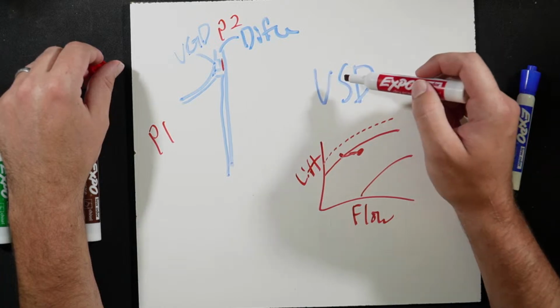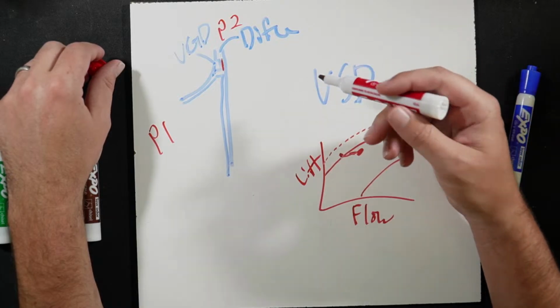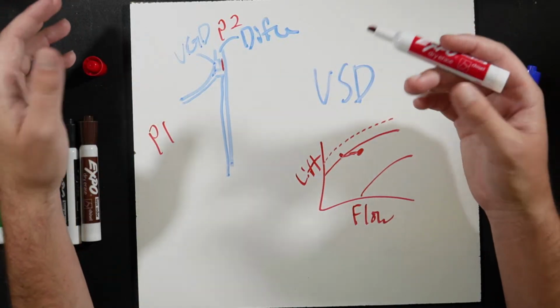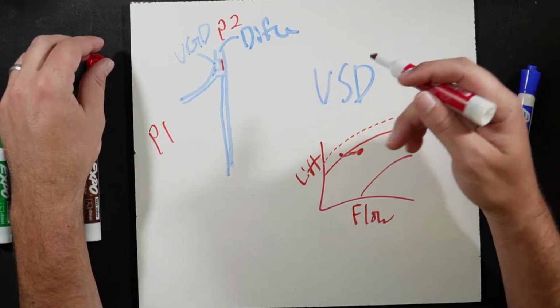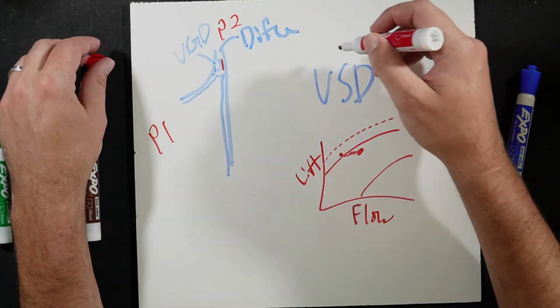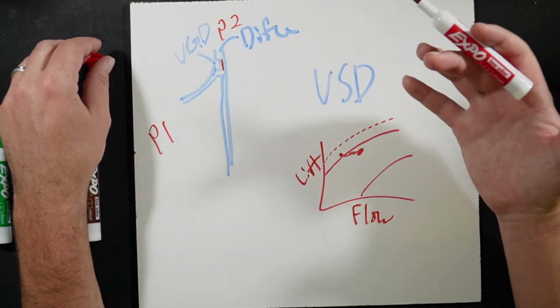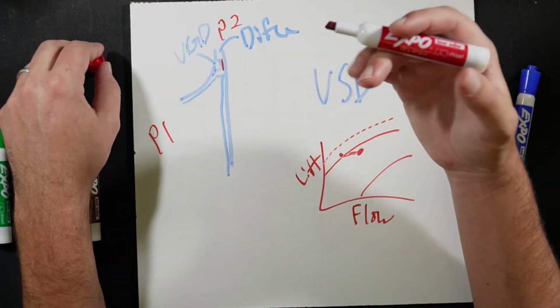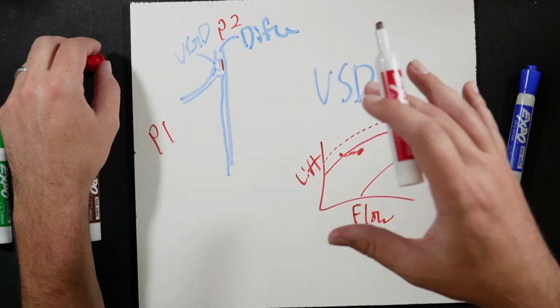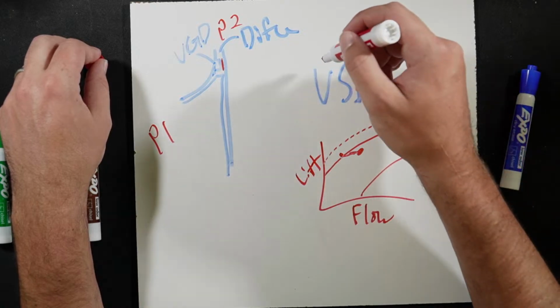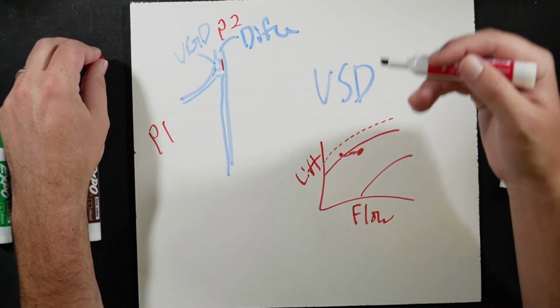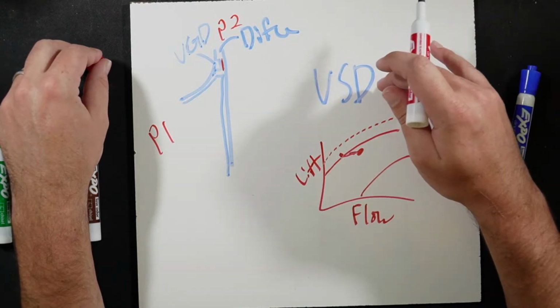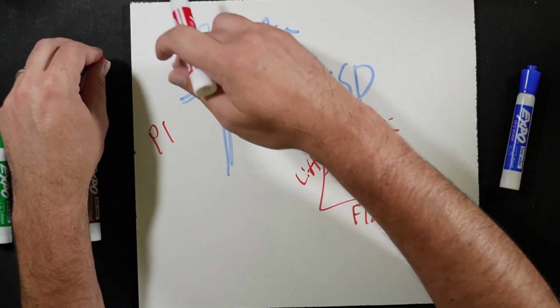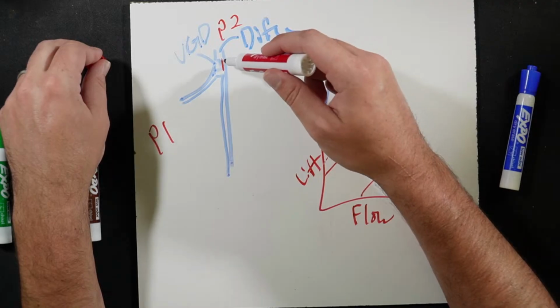if we are trying to unload, but we're having lift issues, and the chiller is pushing the surge boundary, a York machine like these will have a stall detector that is monitoring for when we're pushing into a surge condition. This VGD will still function like it would on any other machine, where it's not even trying to control capacity. It's trying to prevent the surge and stall condition. So in the event that we're running at a part load, but we're not trying to fully unload, the VSD is still the primary load and unload mechanism, meaning speeding up or slowing down the compressor is still the main way we're controlling load. And the VGD at that point, its main job is to prevent the surge and stall condition by modulating this diffusion gap.